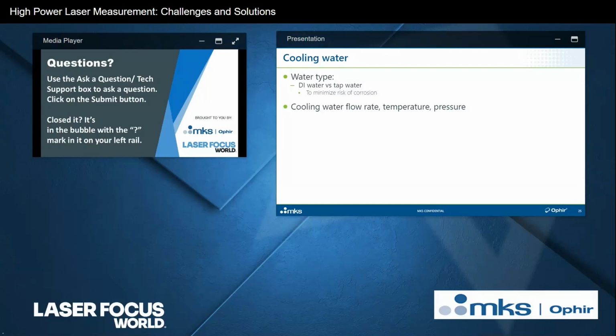Very important is not only the absolute temperature and flow rate of the water, but more important than those is the stability of the temperature and of the flow rate. A slight change in the temperature of the water or its flow rate can lead to a slight change in the temperature of the sensor because the cooling effect changes. The rate at which heat is being removed can slightly fluctuate, and these thermal sensors can generally pick up a change of 1 degree Celsius in a minute. That's how sensitive they are. So as far as possible, you want to keep the temperature and flow rate of the cooling water circulation stable.